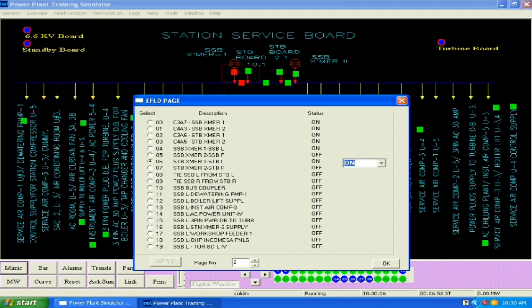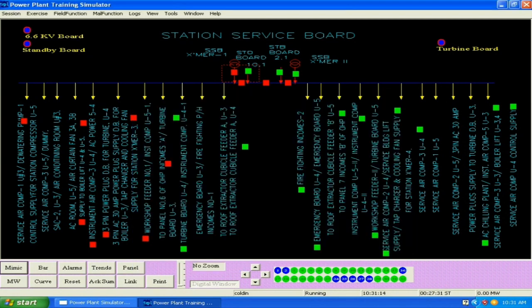Then index number 10 to 18 are the auxiliaries: dewatering pump, boiler lift pump, then instrument air compressor, AC power, then 3-pin power to distribution board to turbine, station transformer 3 supply, workshop feeder, then oil handling plant. Some supply is also given from this turbine board. So all these supplies are to be made on. And then you can go to page number 3 also. One side of the turbine board has been charged.